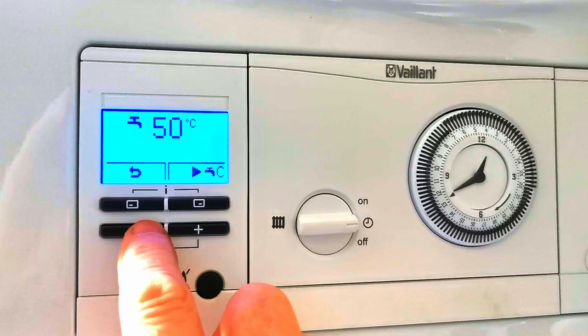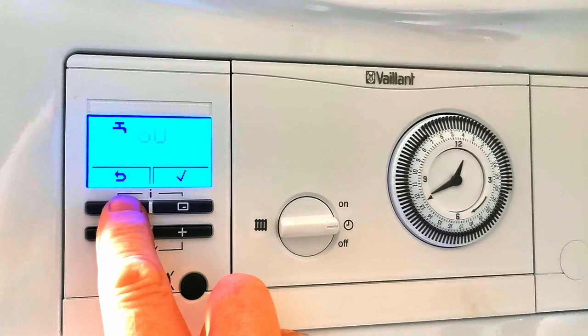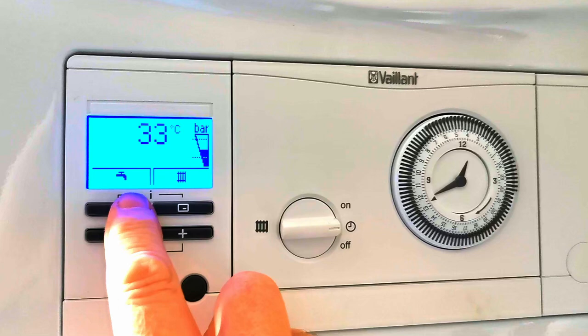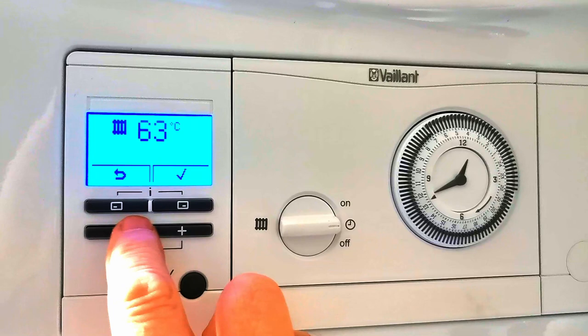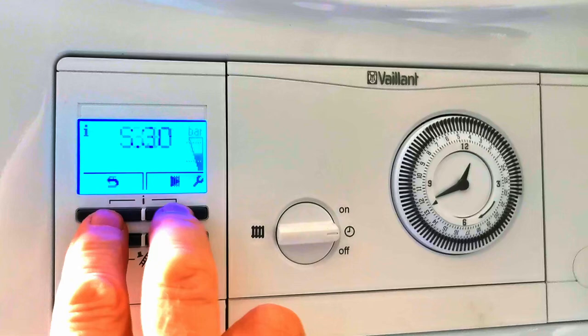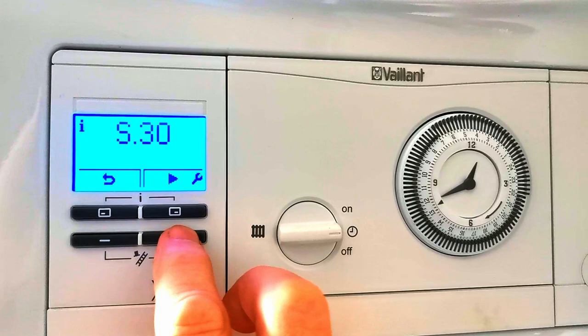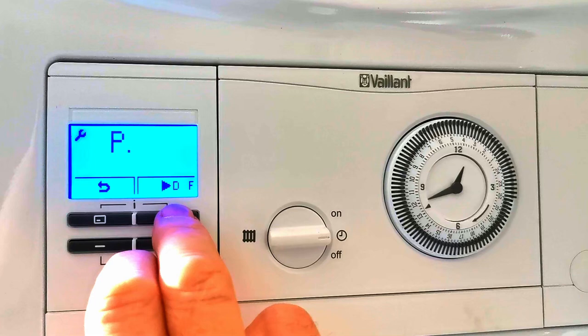This boiler also has a preheat function called Comfort — at the moment you can see it's turned off. We can also easily adjust the temperature that the radiators get to by pressing the plus and minus buttons; this one's currently set at 63 degrees. We can also check exactly how much pressure is in the boiler. The boiler has standard diagnostic S-settings which allow us to check what the boiler is doing in real time, and we can go into engineering mode where we have D-settings and P-settings, as well as fault codes — though those are for engineers.